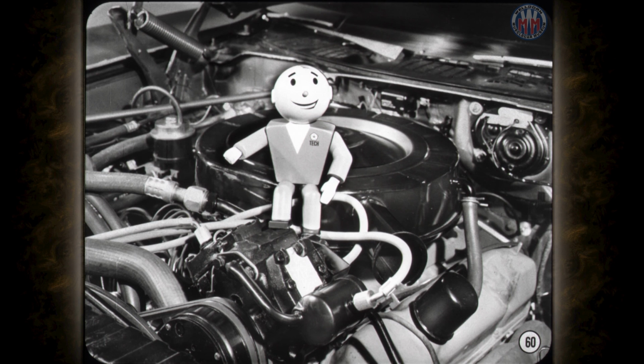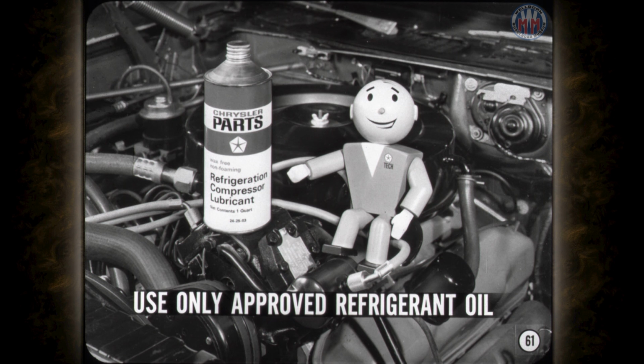the compressor oil level. If system pressure is released suddenly, the oil vaporizes and is carried out of the system by the escaping refrigerant. Be sure to check the compressor crankcase oil level before you charge an empty system after fixing a leak, because low oil level will quickly ruin a compressor. And use only approved refrigerant oil to correct the crankcase level. Engine oil must never be used in a refrigeration system.